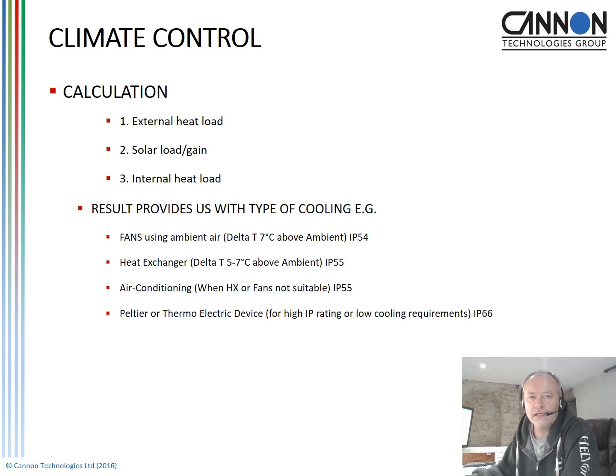So what we look at, as I mentioned, are all of the different types of heat load: the external heat load, the solar heat gain, and the internal heat load from equipment being installed. The results will often tell us whether it's cooling via a fan using ambient air temperature. This is if the customer can operate at an IP54 or IP55 rating using a filter media to bring in that ambient air. We use fans where the delta T, the difference between the internal operating temperature and the ambient external temperature, is above 7 degrees.